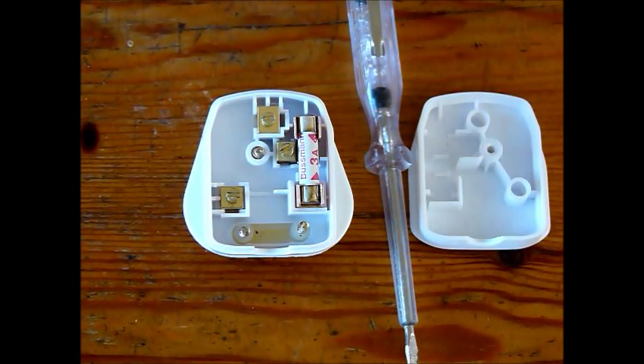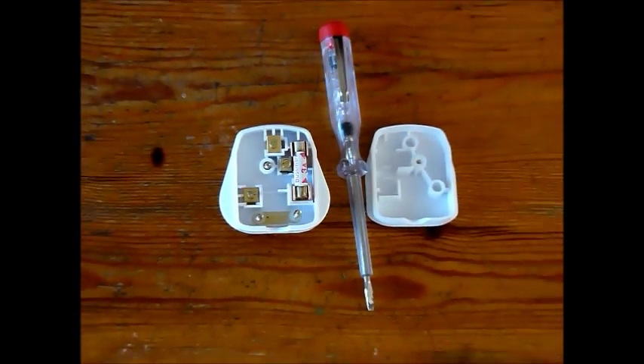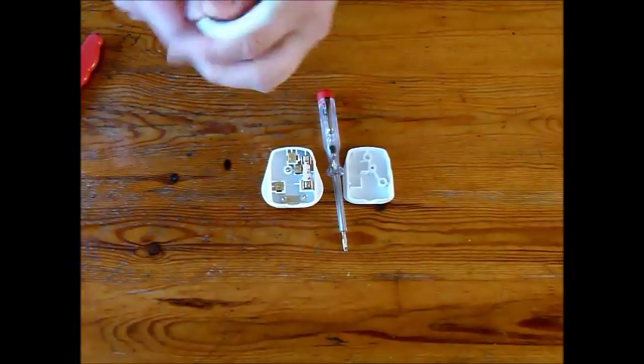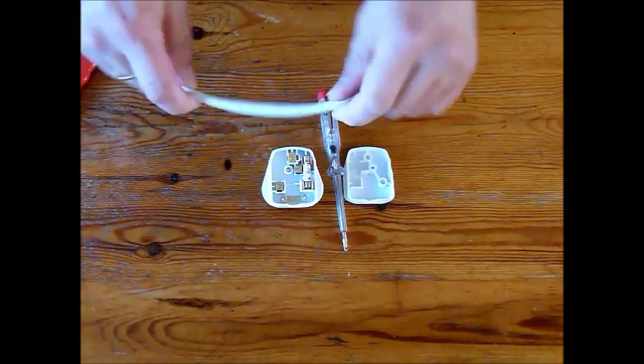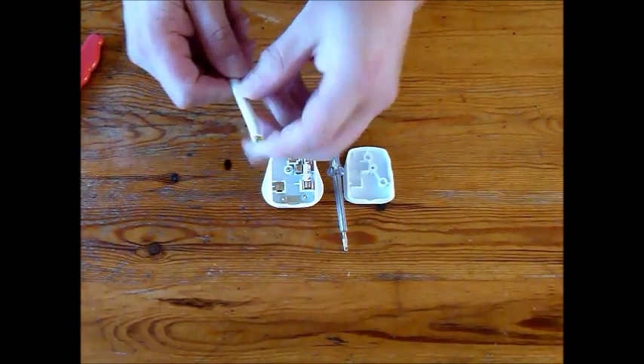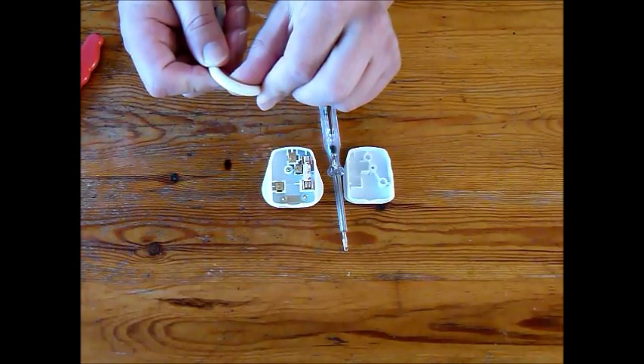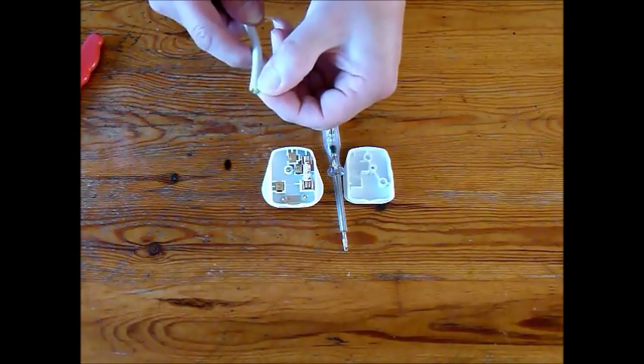Now, 13 amp plugs only ever should be connected to flexible wire. What do I mean by that? Well, if we zoom out a little, let me show you a piece of this. This is flexible wire. The other type of wire you will get is in a flat kind of shape. And it bends and it stays bent. And that's solid core wire. It has inside it solid cores of copper.